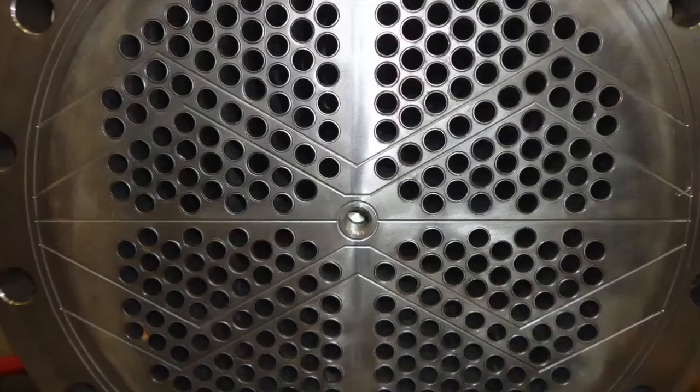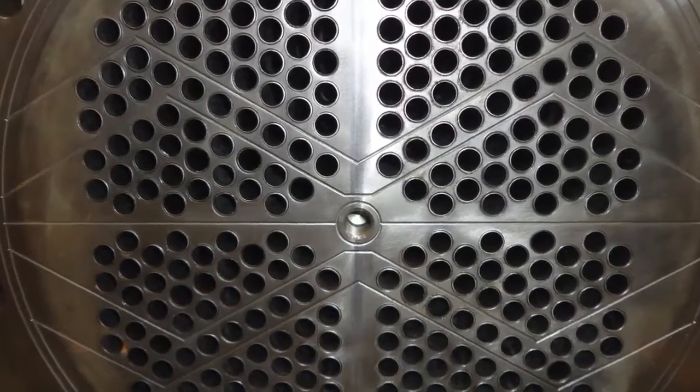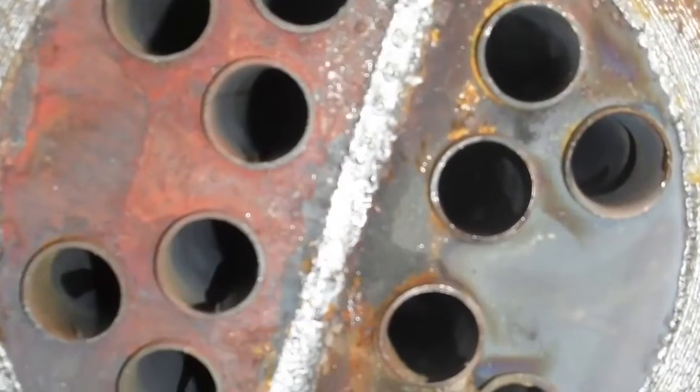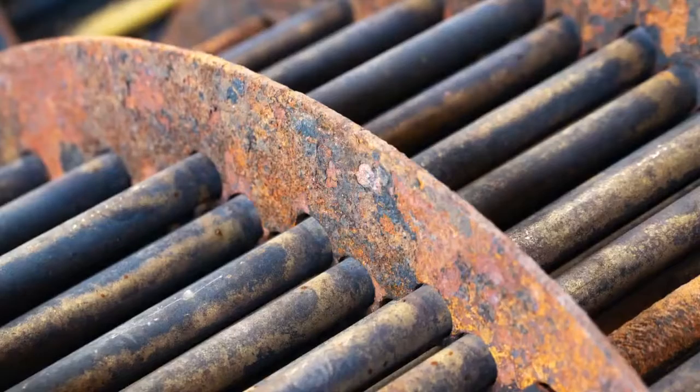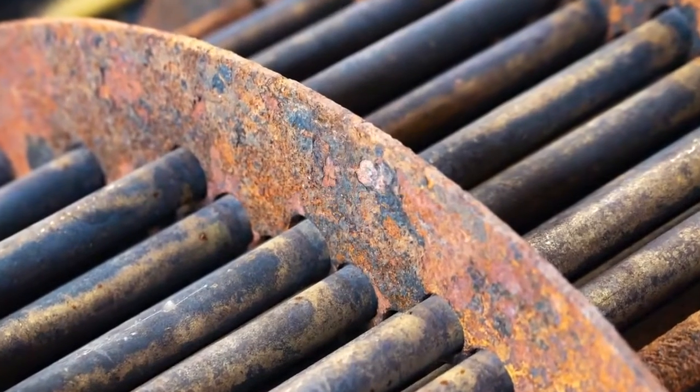In this case, I have a tubular bundle, as you can see from the image, which is made up of many U-shaped fork tubes welded to a single header. In this case, the cleanable part is the mantle's outer part, as the tubular bundle can usually be extracted. Obviously, I can't clean the pipes, because if the pipes reach the bottom and make a curve and come back, it's clear that I can't clean the curve with the brush. Dirty fluid tends to be utilized on the mantle side.